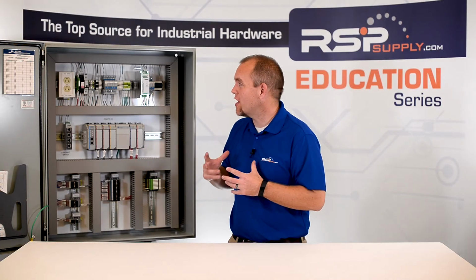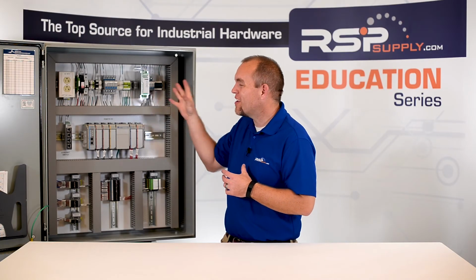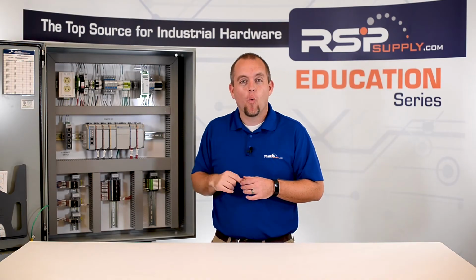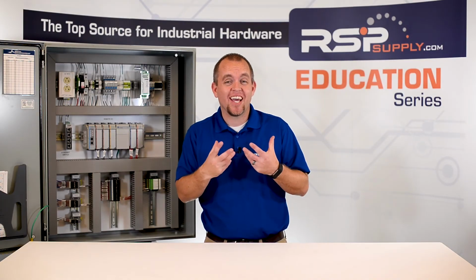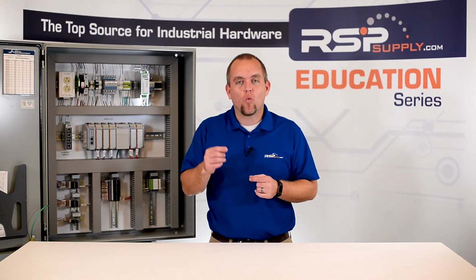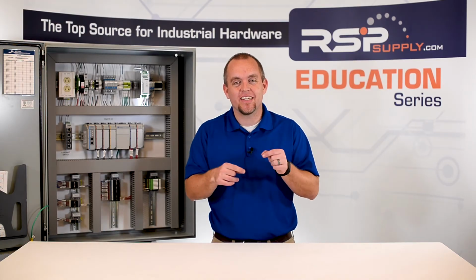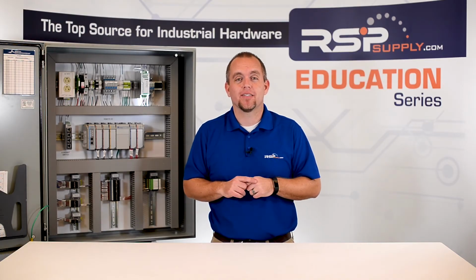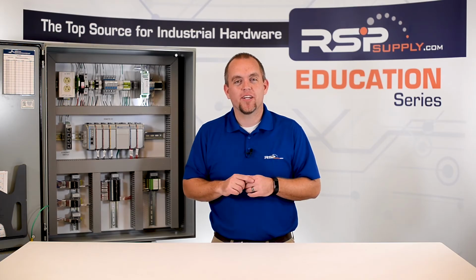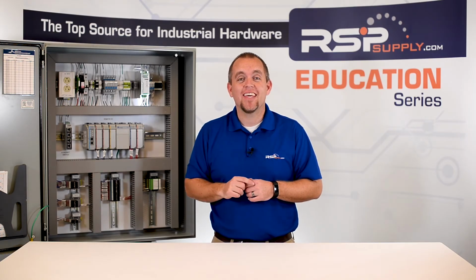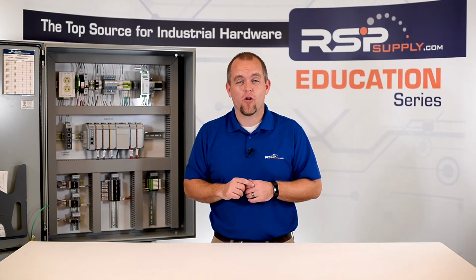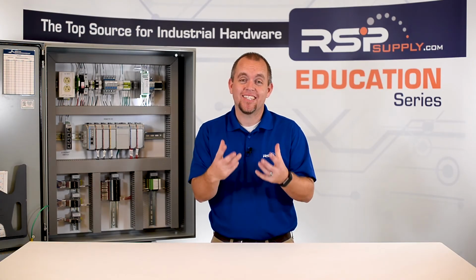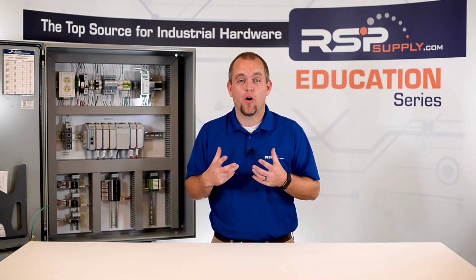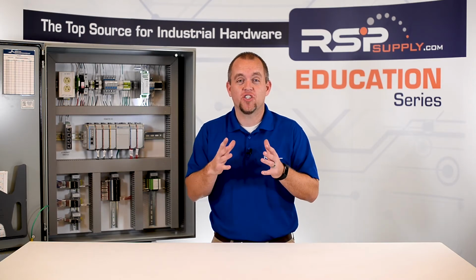We want to make sure that we try to locate that transformer within our power distribution area. We also want to make sure that if we're changing AC voltage, that we change the wire color so that we can easily identify the different voltage types. And lastly, we also want to make sure we have the ability to disconnect the input voltage and the output voltage on the transformer. This allows us to isolate the transformer in case we ever need to operate on it or remove it and change it out.